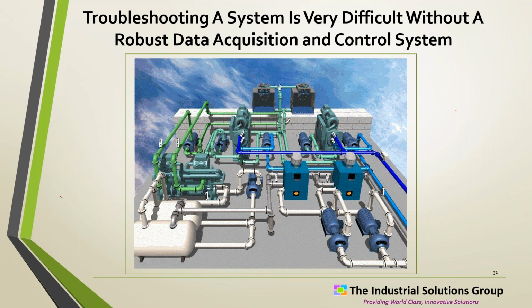Without that robust data acquisition and control system, you could sit there and stare at this system and you can't really tell, because you're dealing with some small differences sometimes. You know, I want chiller temperatures at 10 degrees Celsius. It's 12 degrees Celsius. I can't put my hand on a pipe and figure that out. That's too close, but that's a 20% difference in the amount of cooling that I might be getting on my process. So that could be the difference between having the right humidity and making good product or not.